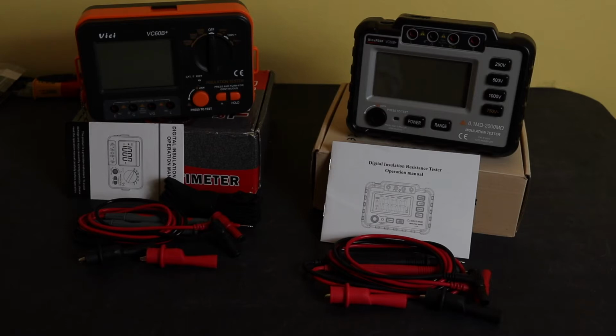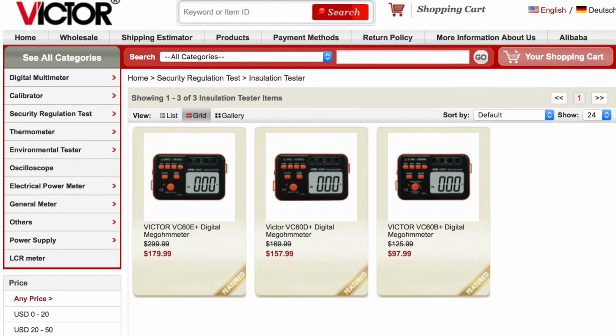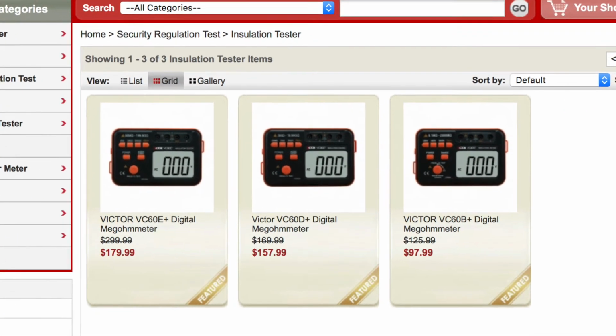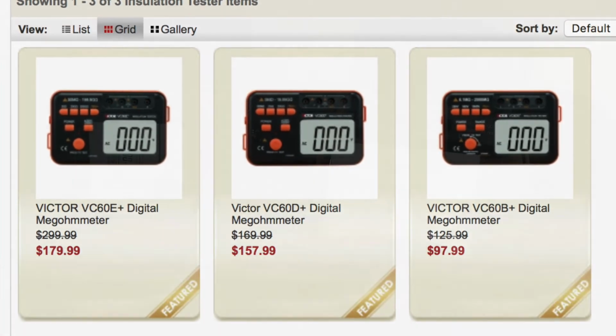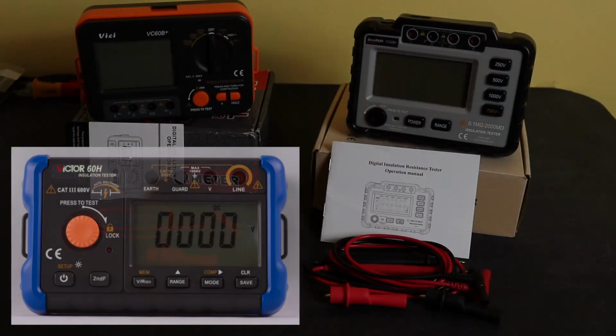Two versions that sit in front of you from different manufacturers, one from Vici, the other one from WinsPEAK, because not only is this one of the cheapest insulation testers out there, it's also one of the most cloned insulation testers out there. There's a myriad of different manufacturers, each with their own little version of this unit. I believe that the original manufacturer of the Vici 60B is a company called Victor Instruments. They make a few derivatives of the Vici 60. They make the B version, as you see here. They make the D version, which is 1000 volt and 2500 volt. And they make the E version, which is 2500 volt and 5000 volt. And they make the H version, which is a 100 volt to 1000 volt unit.